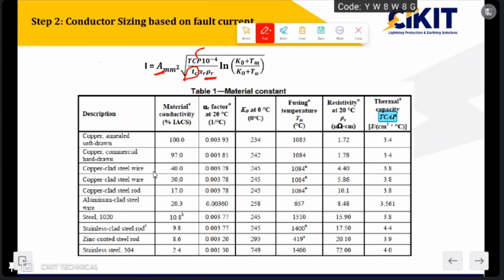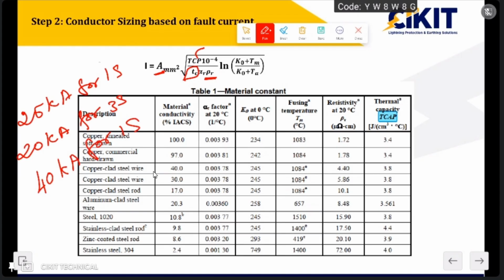In general, the fault current rating of any substation will be mentioned as either 25 kA for 1 second, 20 kA for 3 seconds, or 40 kA for 1 second. Whenever they mention the fault current, they will always mention the duration along with it, because the current carrying capacity of the conductor mainly depends upon the duration. If the duration is higher, the current carrying capacity will be lower. If I take one particular conductor as an example, the current carrying capacity will be much higher for 1 second, but if I take 3 seconds, the current carrying capacity will be lower. So the duration of the fault current is one of the important parameters that has to be considered for calculating the current carrying capacity.